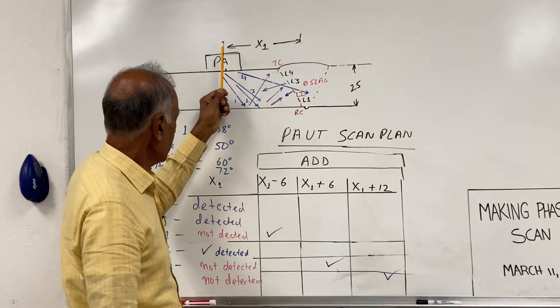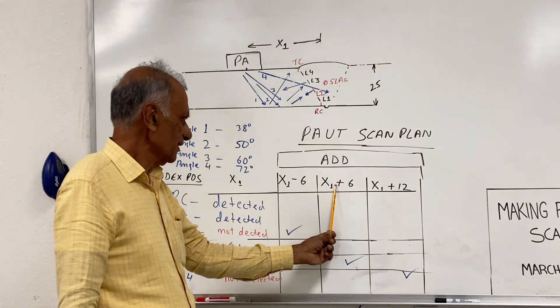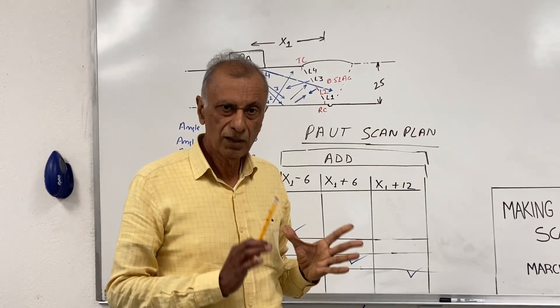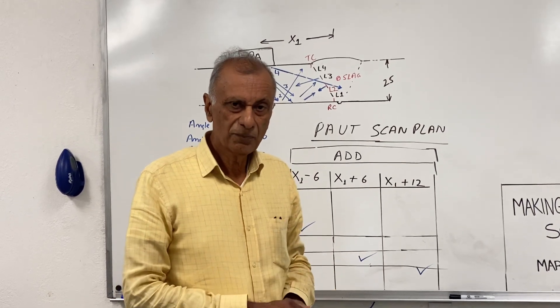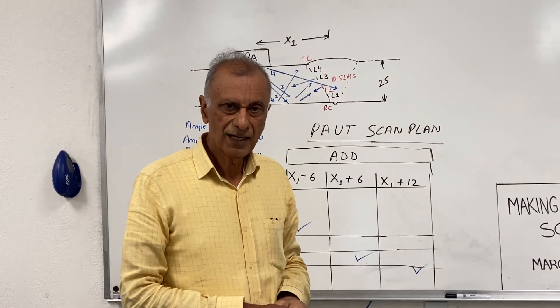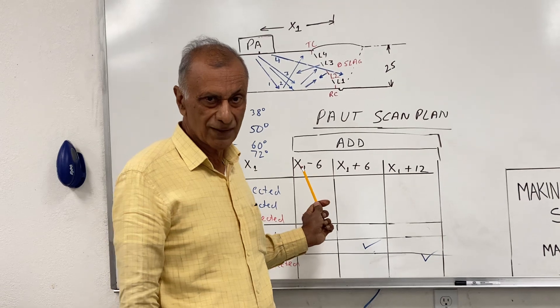We scan at position X1, then X1 minus 6mm, X1 plus 6, and X1 plus 12, to get not only the full illumination of the weld, but also to make sure that we can detect all the lack of fusion flaws, which are shown here as L1, L2, L3, and L4.